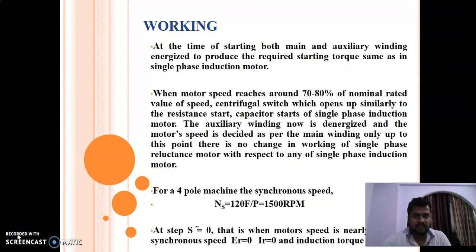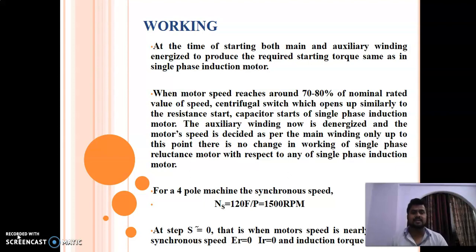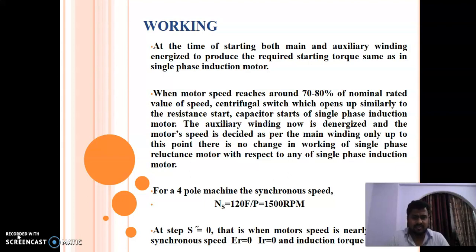Now let us come to the working. At the time of starting, both main and auxiliary windings are energized to produce starting torque. A rotating magnetic field is produced with the help of the main and auxiliary windings, and the reluctance motor is started as a single-phase induction motor. When the motor reaches a speed of around 70 to 80 percent of its nominal rated value, the centrifugal switch operates and opens the auxiliary winding, similar to the case of a resistance-start or capacitance-start induction motor.